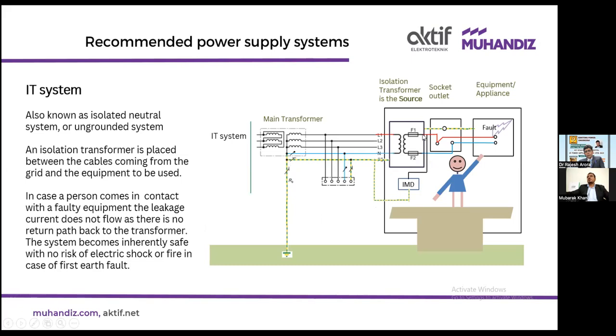In the same situation, when there is a fault and a person touches the body, there is no way the current can return to the source. In this case, the source is the transformer. It has created isolation between the main circuit and this particular room, which is why the transformer has become the source. There is no way the current can flow back to the source, so the leakage current will not flow and this person will not get a shock, even in a fault condition. If we replace this person with a wire directly from the body to the ground, there will still not be any leakage current. There is no risk of fire.